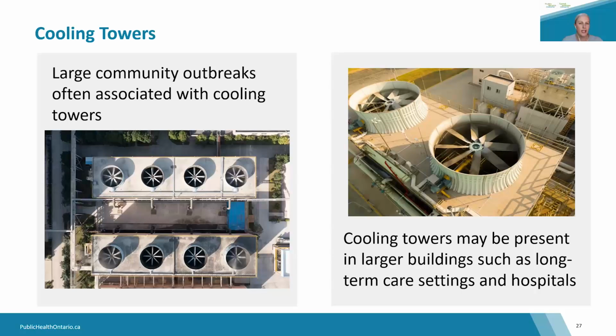So if cooling towers are not maintained properly, they can result in large community outbreaks, which was seen this past summer with an outbreak locally in London, and also a large outbreak that happened in New York. Also, as Maurice previously mentioned, that large and devastating outbreak at a long-term care home in Toronto back in 2005 was associated with a cooling tower at the facility. So really proper operation and maintenance of cooling towers is very important in preventing Legionella growth. And there are resources provided at the end of this presentation that would support recommended operation. It is worth noting that most window air conditioning units and car air conditioning units do not use water to cool the air, so they're not a risk for Legionella growth or spread. Next slide, please.